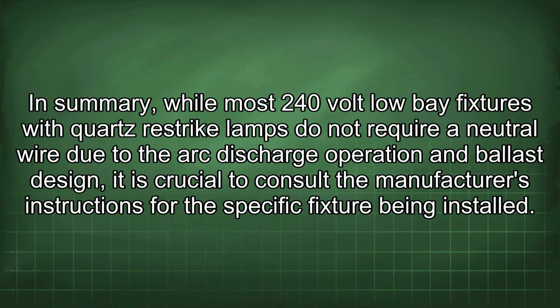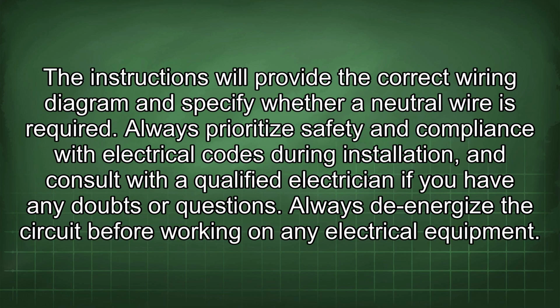In summary, while most 240-volt low-bay fixtures with quartz restrike lamps do not require a neutral wire due to the arc discharge operation and ballast design, it is crucial to consult the manufacturer's instructions of the specific fixture being installed. The instructions will provide the correct wiring diagram and specify whether a neutral wire is required. Always prioritize safety and compliance with electrical codes during installation and consult with a qualified electrician if you have any doubts or questions. Always de-energize the circuit before working on any electrical equipment.